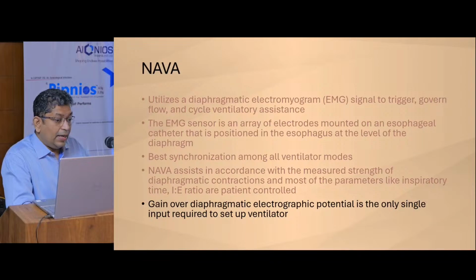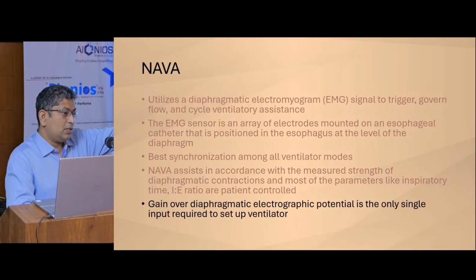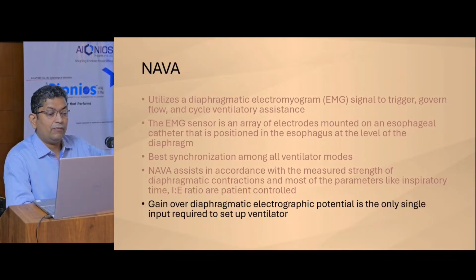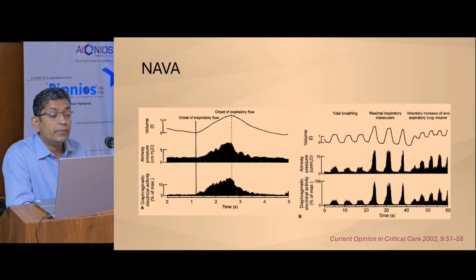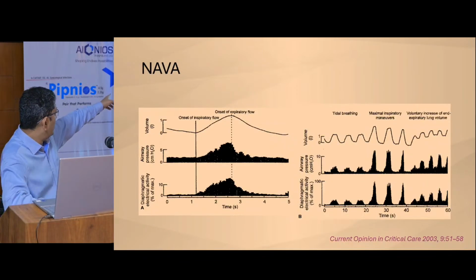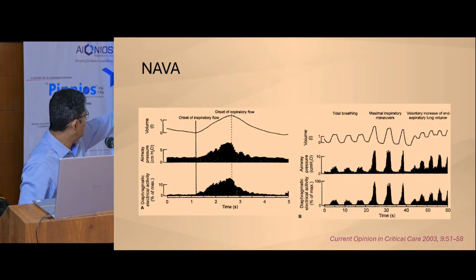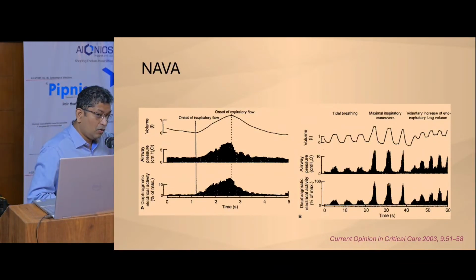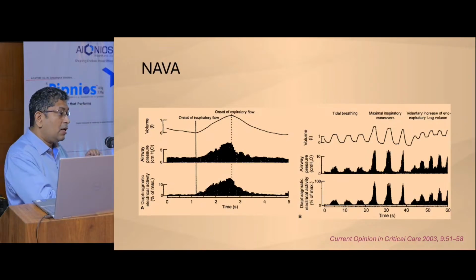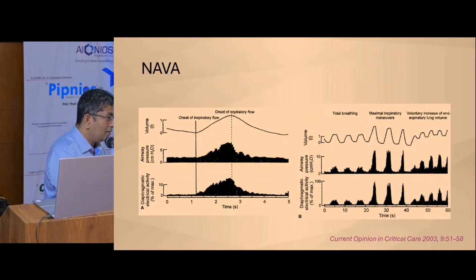What you have to set is the gain. So you have the electrical signal, and based on that, how much pressure you have to give, less or more, can be set using the gain. That's what you have to basically set. So that's the electrical myograph, and that's how the breathing pattern will go. As you said, the best synchrony, very wonderful.